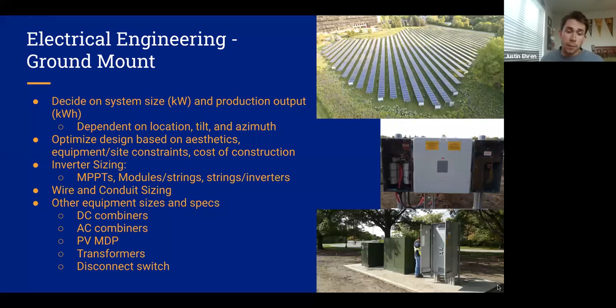Finally, there's a number of different equipment that we go through and utilize for the systems: DC combiners to bring the DC string wiring together, AC combiners to take the multiple inverter outputs and combine them to reduce wiring on the AC side. For large projects, we sometimes have a PV main distribution panel, which combines multiple AC combiners. Transformers are often used to get our voltage to what we need, whether that's medium voltage interconnecting at the grid or stepping it down to a lower voltage like 120/208 volt so we can interconnect at the building.